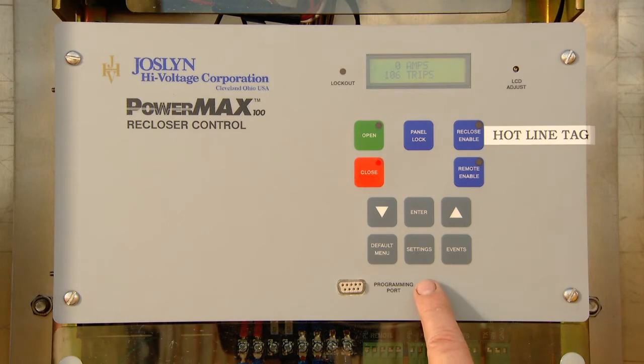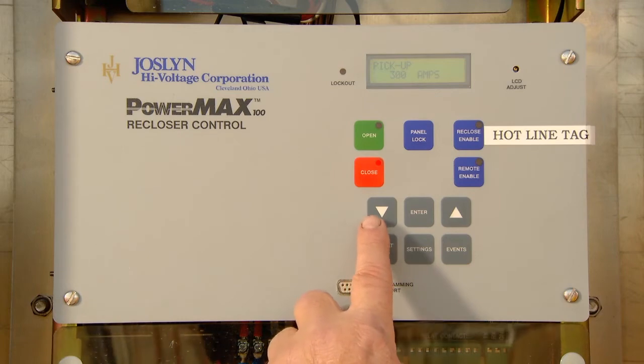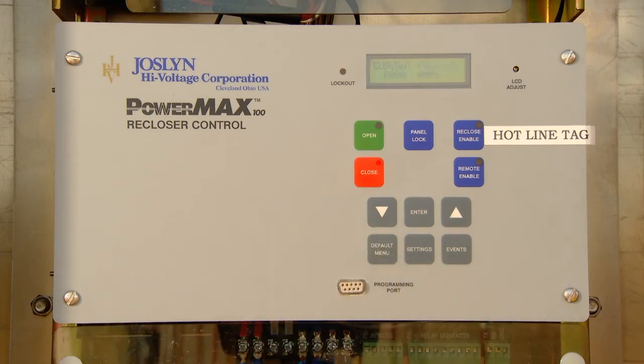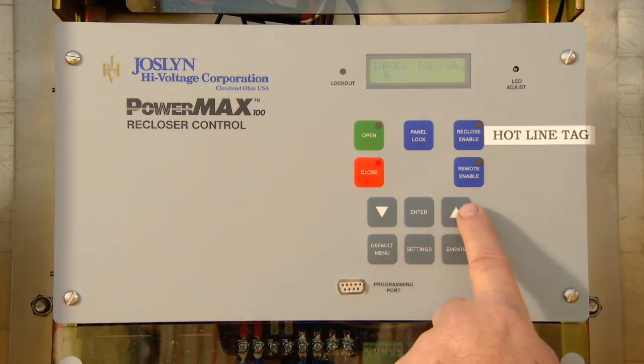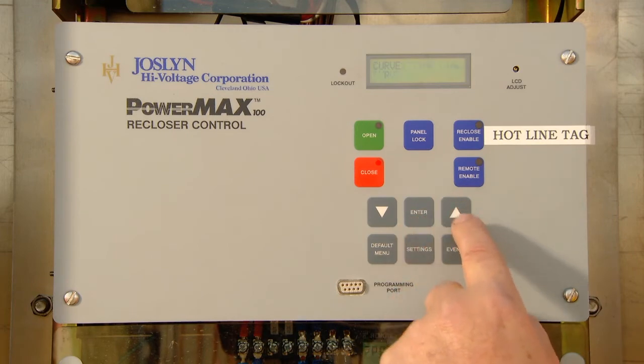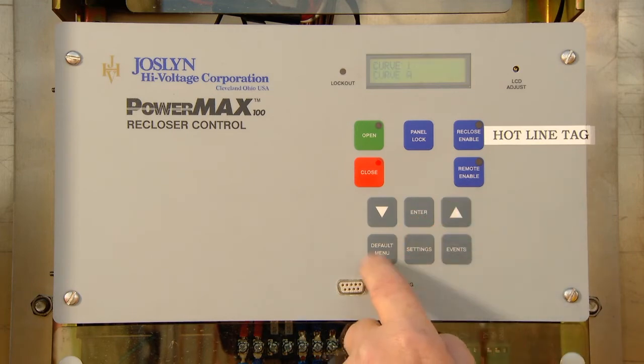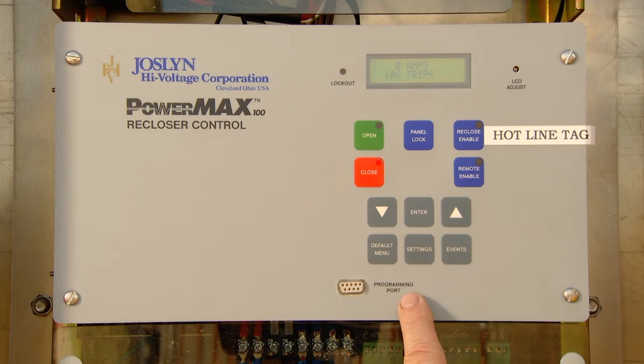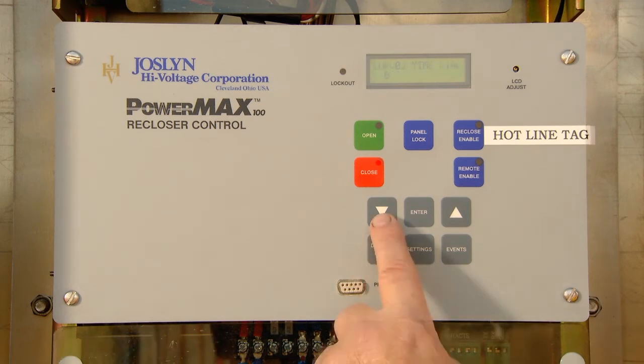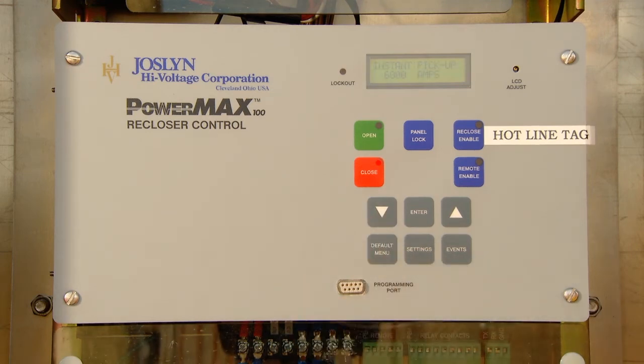To display the settings, press the Settings button to display exactly what the pickup is programmed for, in this case 300 amps. Now, by pressing the scroll arrow down, you can see that the fast curve for this unit is an A curve. Press again to display the second or slow curve, in this case a B curve. Press again to display instantaneous pickup.